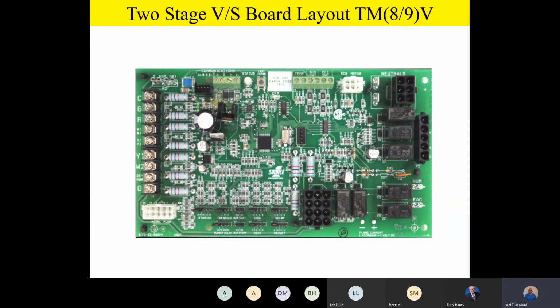So as we take a look at our two-stage variable speed board, this will be the control board we're going to find on the TMV product, the TM8V and the TM9V product, meaning variable speed. Now this is a high efficiency motor as well, but it's a full variable speed board. The big difference between this and the previous boards is that instead of setting up airflow by selecting a speed tap and a physical wire that you're going to change on the motor itself, this board's going to give you some jumpers to select airflow. So that's the big thing with the variable speed.